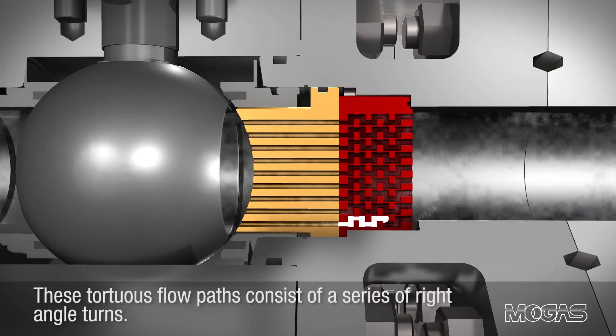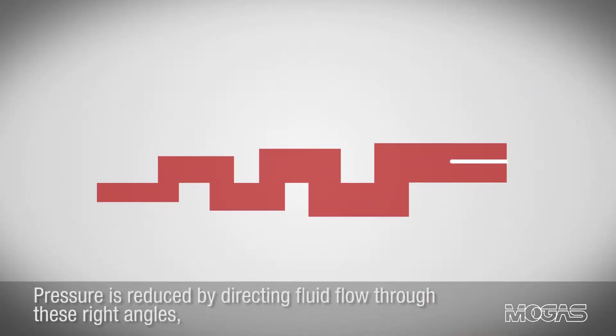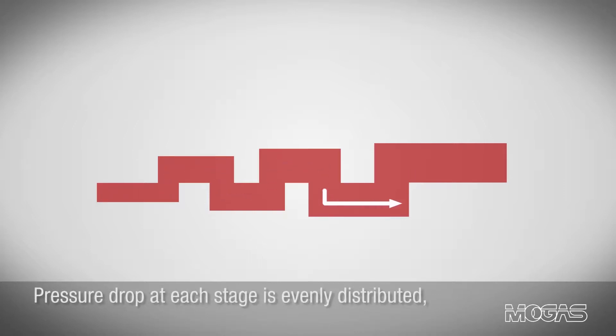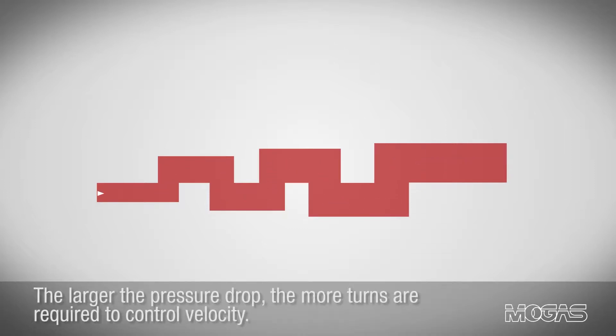These tortuous flow paths consist of a series of right angle turns. Pressure is reduced by directing fluid flow through these right angles, which control kinetic energy and velocity. Pressure drop at each stage is evenly distributed, while the tortuous path expands at each right angle to ensure velocities will not be increased. The larger the pressure drop, the more turns are required to control velocity.